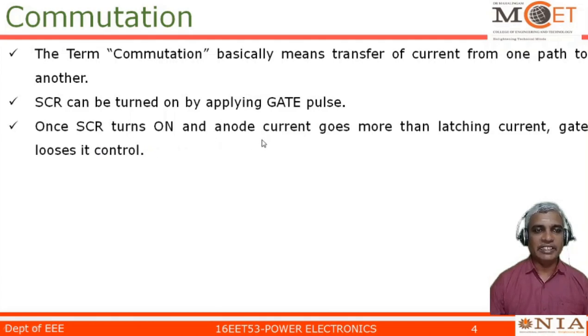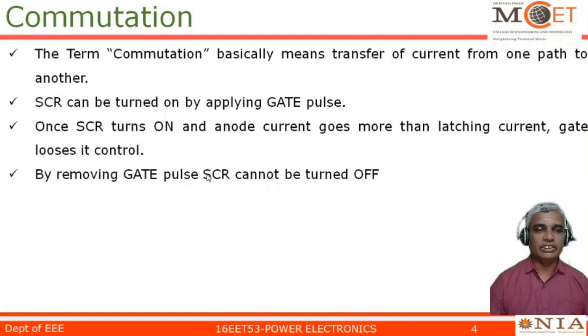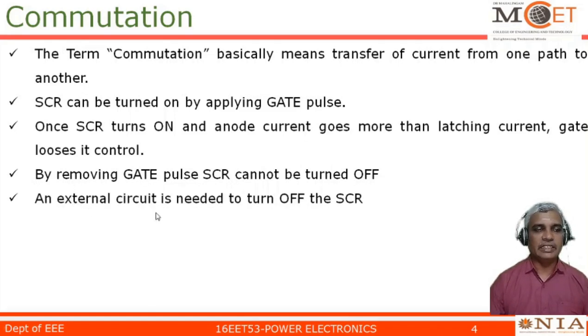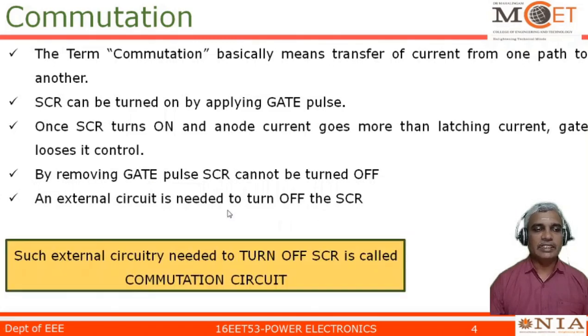During the turn-on process, I apply the gate pulse. Once the anode current becomes more than the latching current, the gate loses control, meaning I can remove the gate pulse. Removing the gate pulse does not mean that SCR will be turned off. The turn-off process has nothing to do with the gate pulse — gate pulse and turn-off process do not have any relationship. To turn off an SCR, some external circuitry is needed, and such external circuitry is what we call the commutation circuit of an SCR.